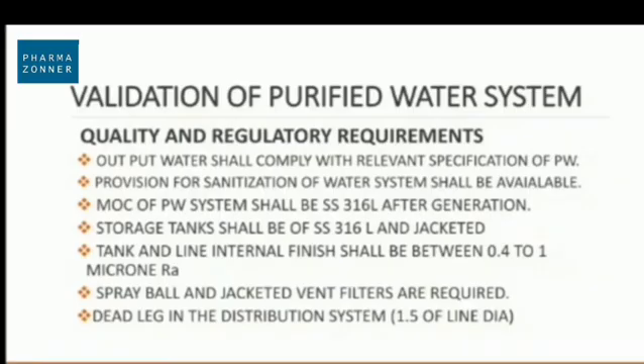Regarding quality and regulatory requirements — air and water together make up 50% of pharmaceutical requirements, so water systems are very important. We need to know regulatory requirements to avoid gaps during audits or pharmacopoeial compliance checks. First, the output of the water shall comply with the relevant specification of purified water. There should be provision for sanitization of the water system — either hot water sanitization or steam sanitization.